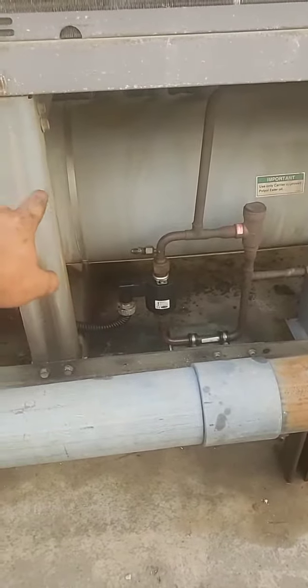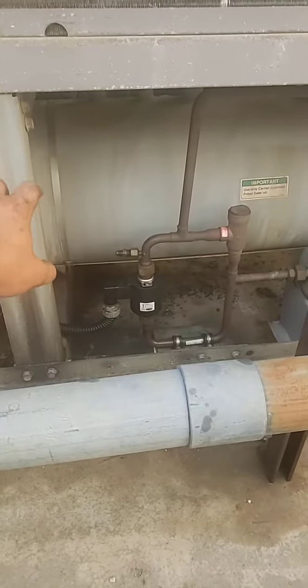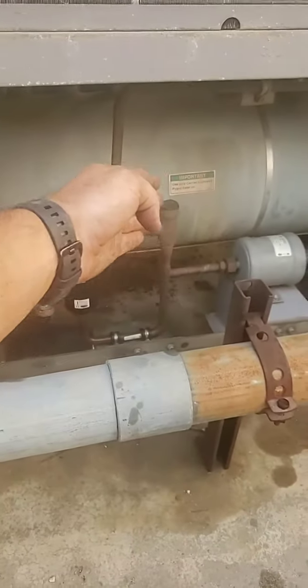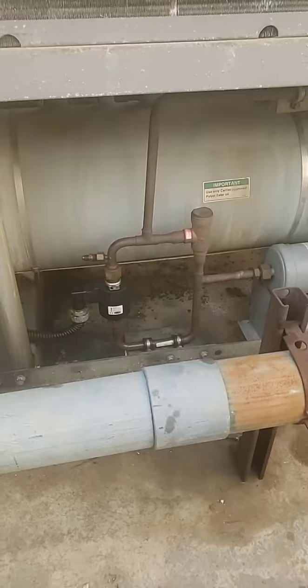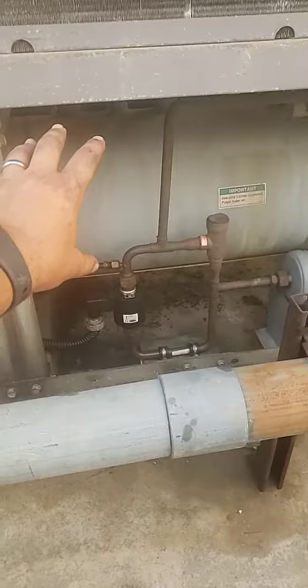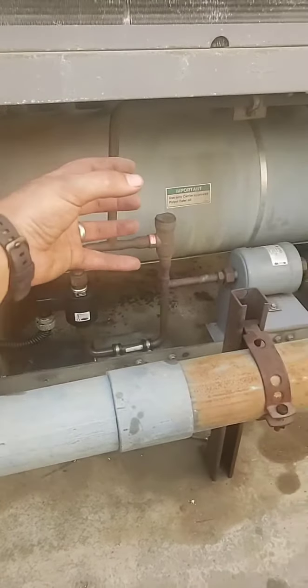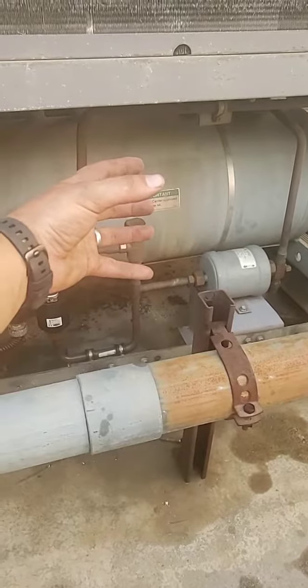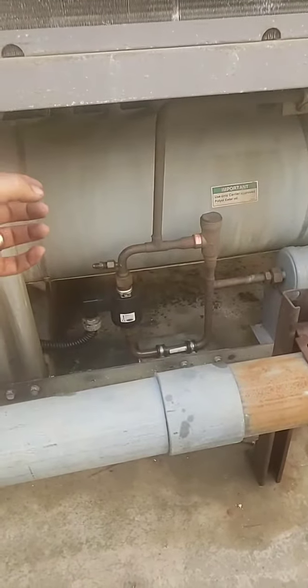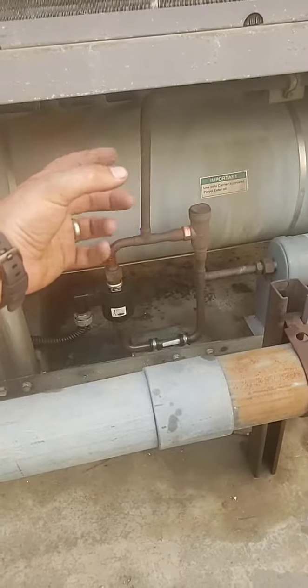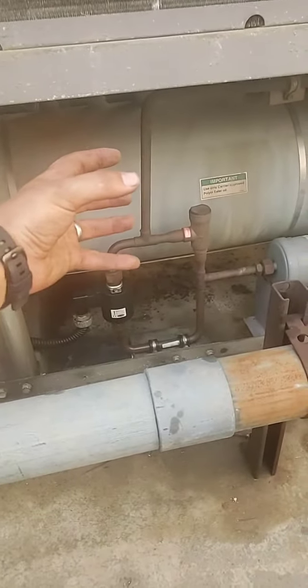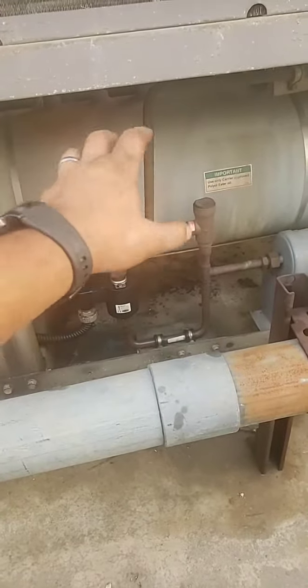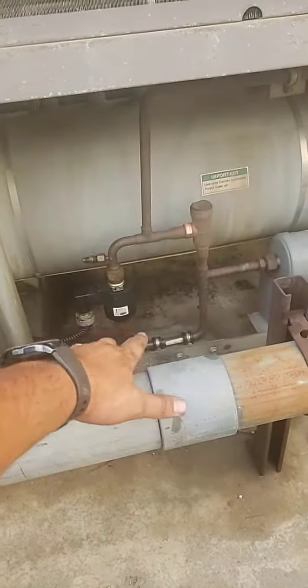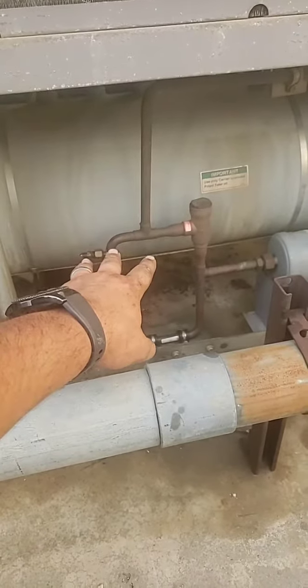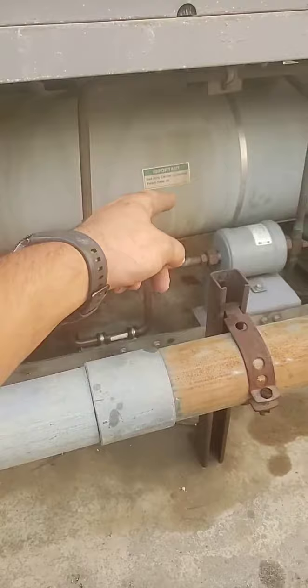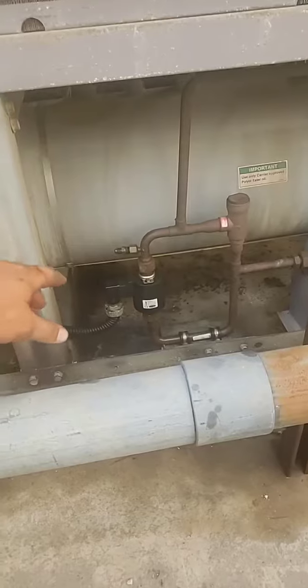The baffles look kind of like a wire screen mesh most of the time, and they'll be distributed throughout this chamber. What they're literally doing is, as the hot gas from the discharge flows through, and it's got a heavy oil saturation on it, that oil clings to the wire mesh inside of the oil separator. As it catches it and clings to it, it then begins to fall back down into the bottom and get recollected in the oil separator itself, and then gets pumped back out and back into the compressor.